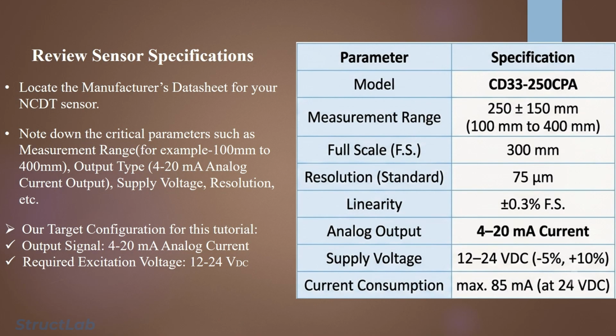Locate and review the manufacturer's datasheet for your specific non-contact displacement transducer. Before making any electrical connections, it's important to note key parameters, namely, the physical measurement range, the available output options, and the required supply voltage. For this specific tutorial, we'll be working with a 4 to 20 mA analog current output model, which needs 12 to 24 volts DC excitation.